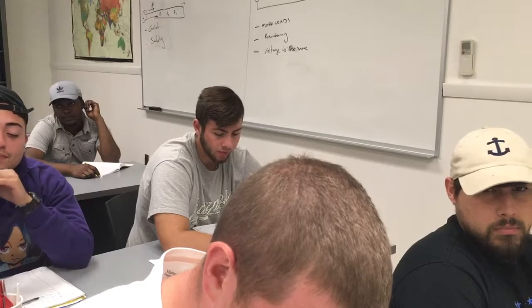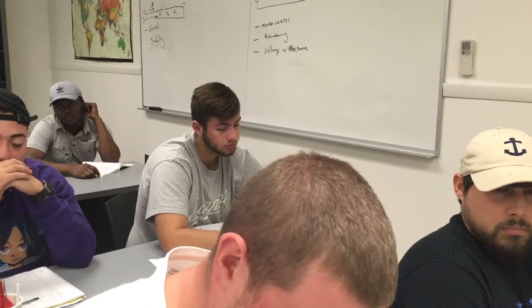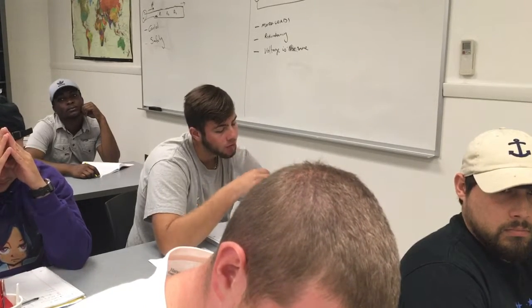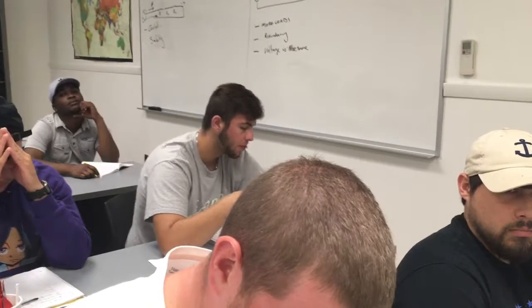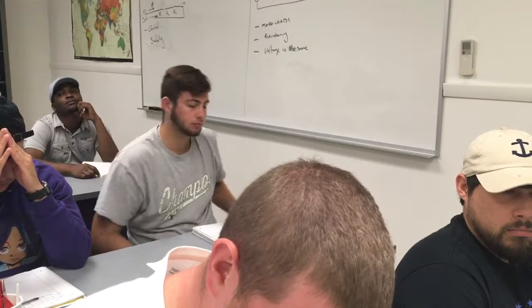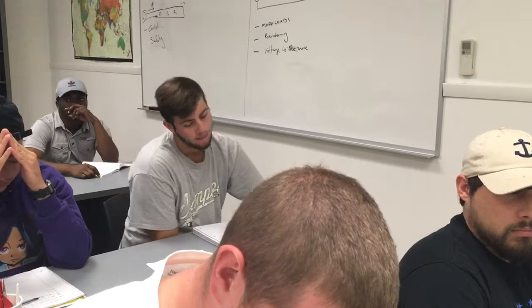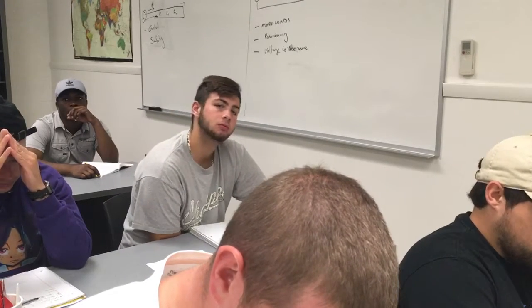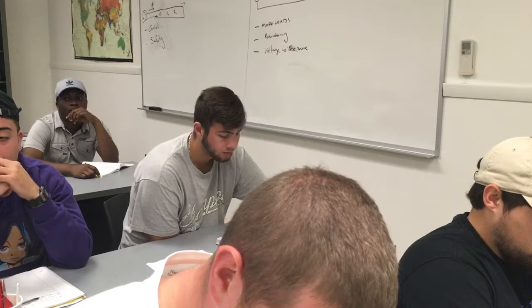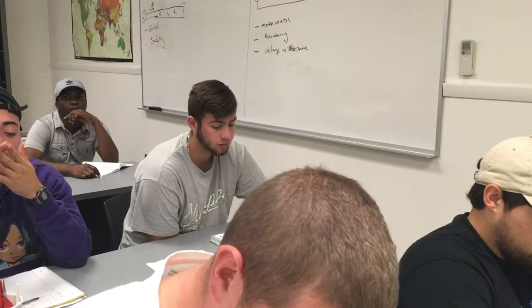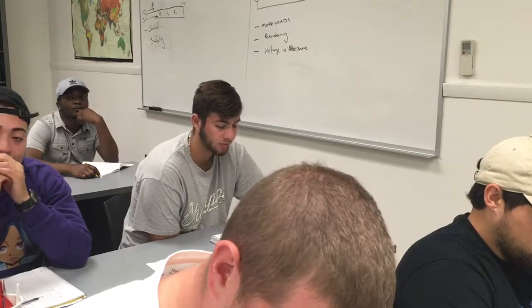Again, they're not going to look this way. It's not going to look as simple as this on paper. In reality, you'll see the wire goes and it forks, and you put a pigtail in it, 3, 4, 5 loads, and it splits more and more. So the key thing to remember is if you split the current, it's parallel. If the current is in the same wire, then it's in series.